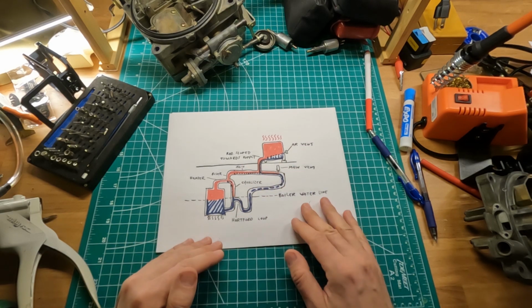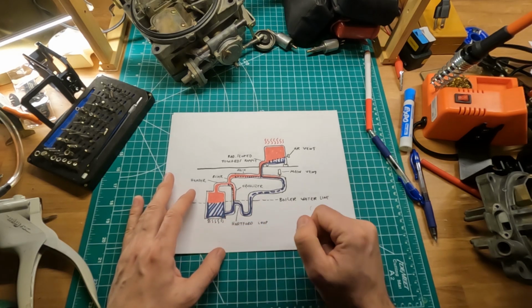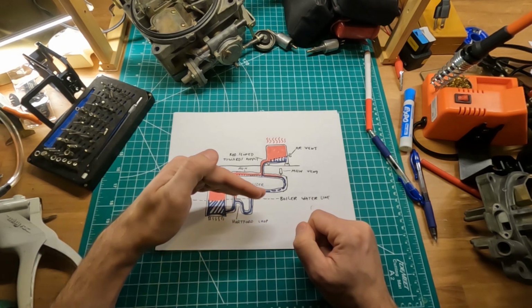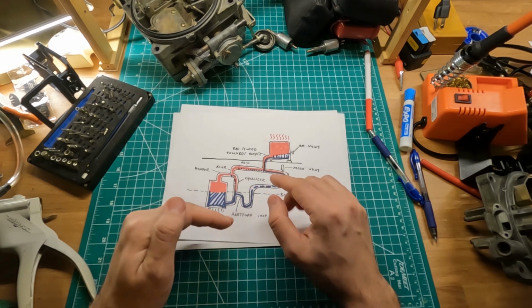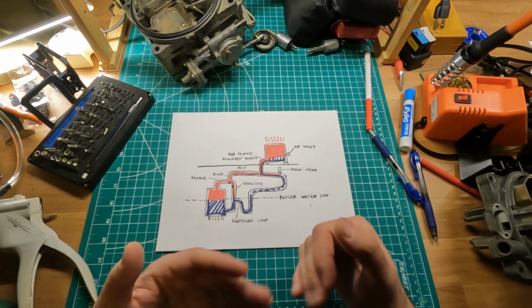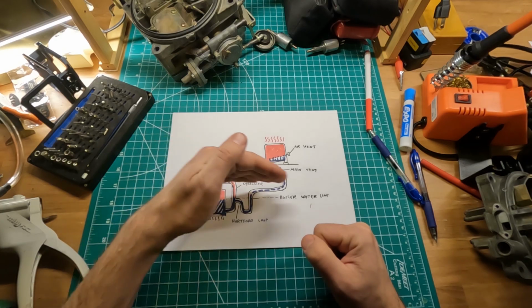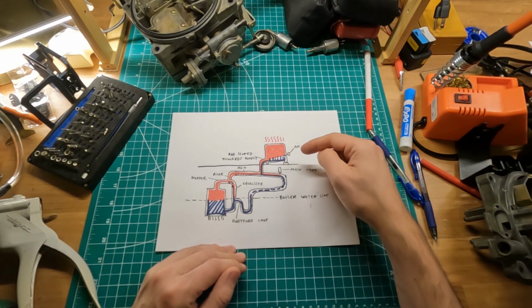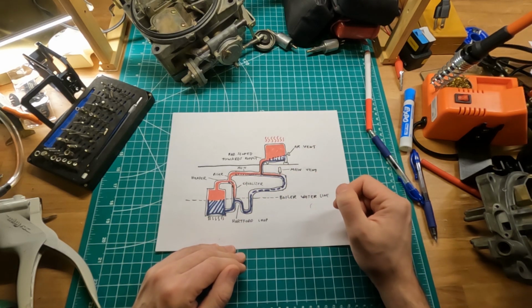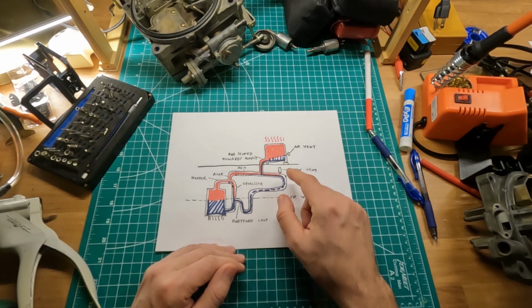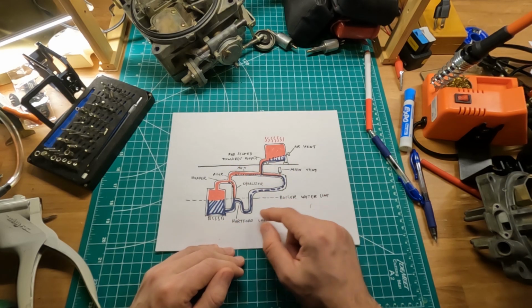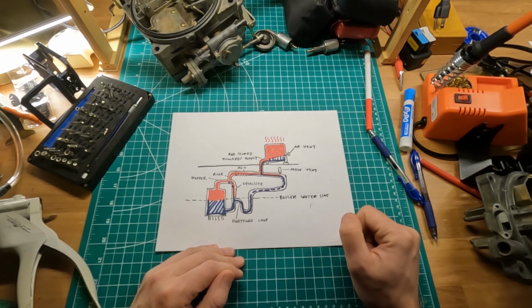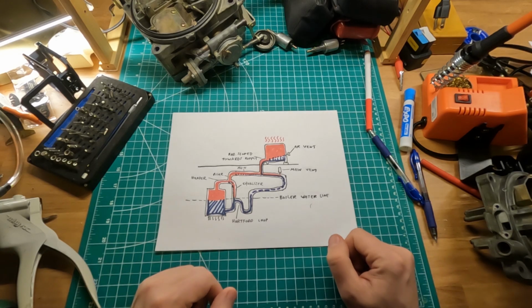That's basically it. In essence, the fundamentals: steam goes here. The pitch of the pipe is very important, so that via gravity the condensate knows which way to flow. The pitch of the main pipe is important. The pitch of the radiator is important, so the water doesn't accumulate in any places, but rather continuously keeps flowing where it's supposed to go to return to the boiler. And that's basically it. Hope it was helpful.